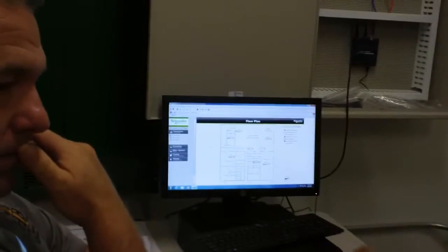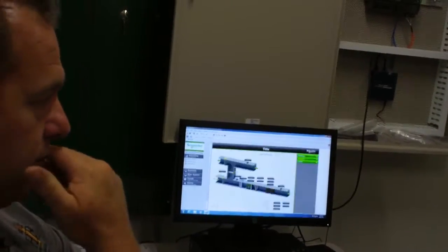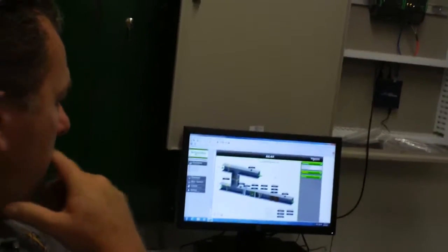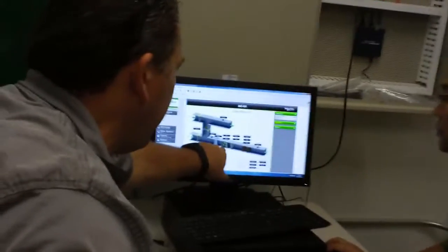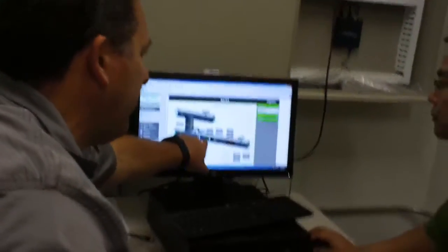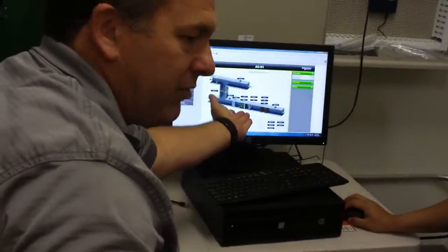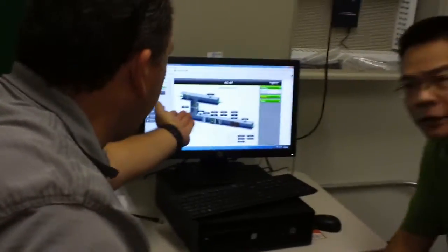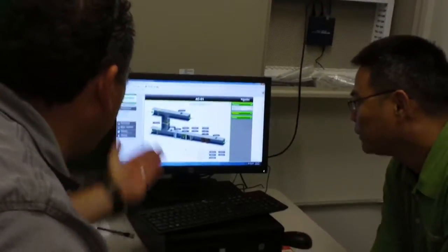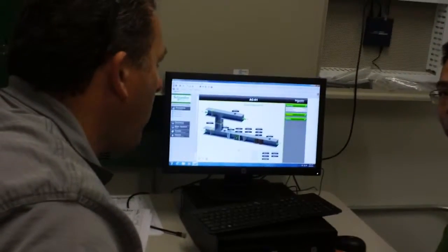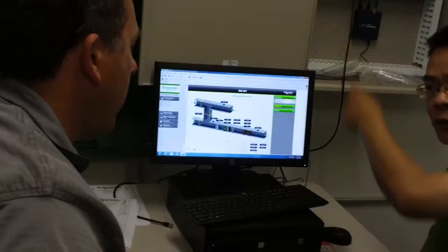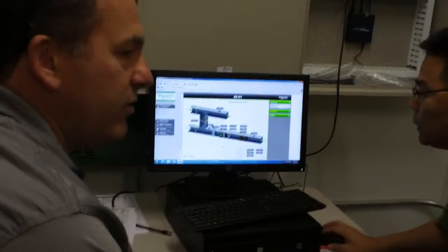Is there remote access at all, or no? Not yet, but I think in about a week they're going to give him access. Okay, good. So what I'm saying is, if that's still spinning, we may have a broken belt. We have no indication of low amps. Any static pressure? We don't have static pressure. We have static pressure for the 4 units. It shows those units as DAV.